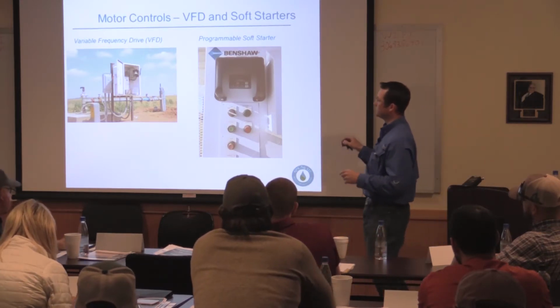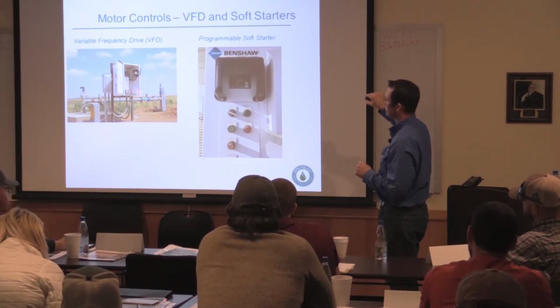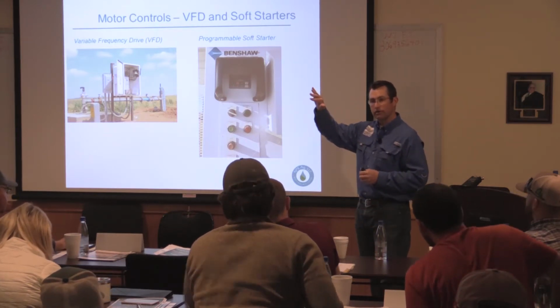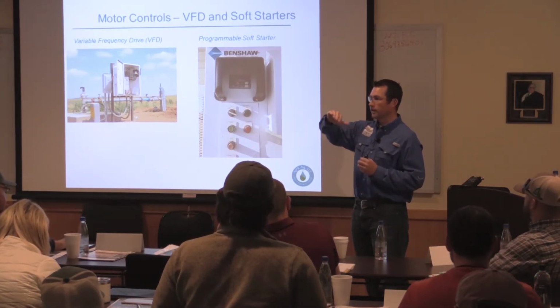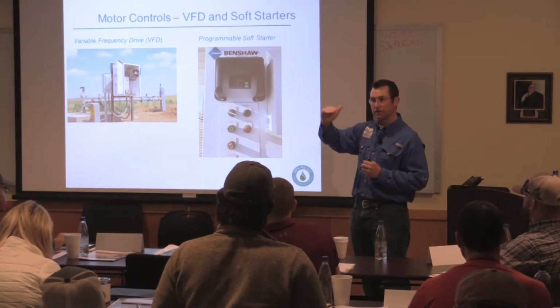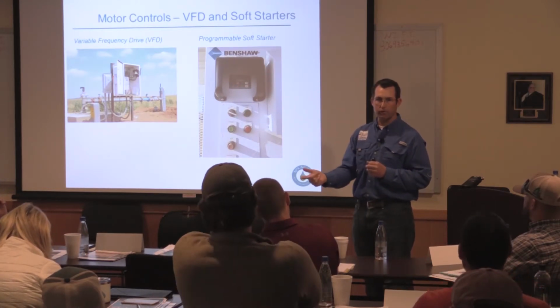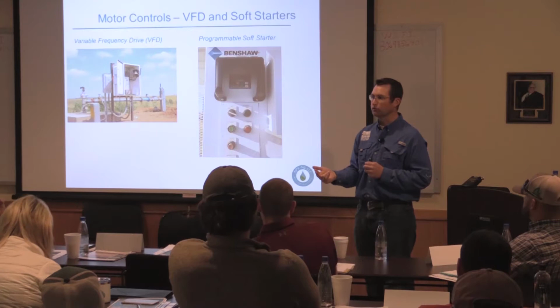Okay, so what you want to have these controls for is a drive so that you can ramp that start, but also so you can then dial in the speed of your motor by changing the frequency so that you don't overpump and subsequently so you don't overload the generator.